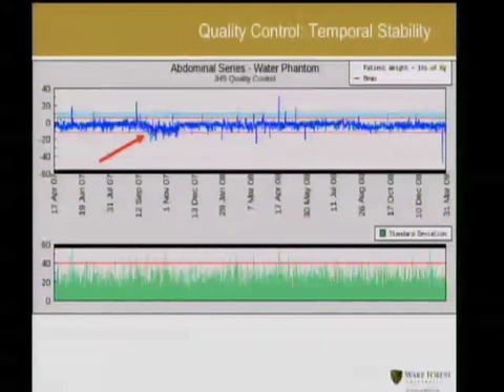Now in this protocol, we're also doing the chest CT on the same scanner, and we didn't see it. What happened was somebody, during a service call, switched a parameter. It was the pitch value of the helical scan, and we were able to identify it within 2 weeks and fix it without having this offset through the entire scan. So quality control is what I do all the time. You can never do too much quality control.